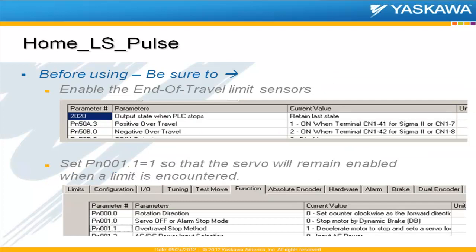Before using this function block, be sure to first enable your end-of-travel limit sensors, and then second, it's highly recommended you set parameter 1.1 equal to 1. It will default to 0, which means that when you hit an end-of-travel limit, the axis will disable itself in that direction. Setting it to 1 will decelerate the motor to a stop and set a servo lock condition — basically, just keep it enabled.